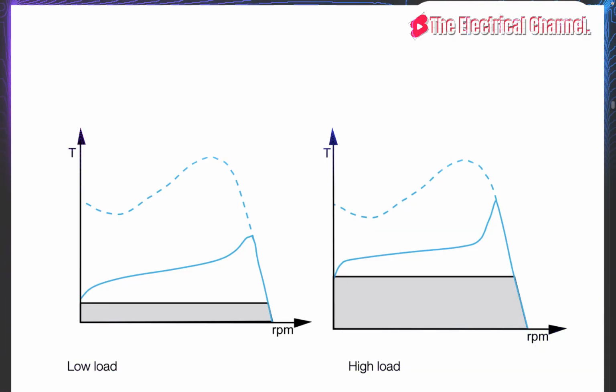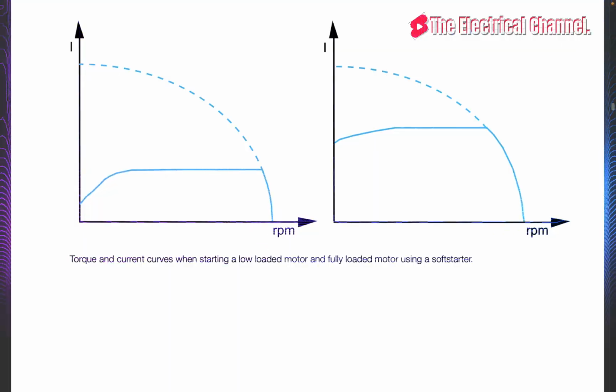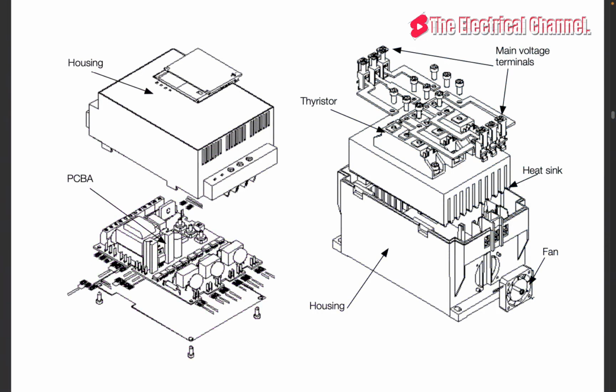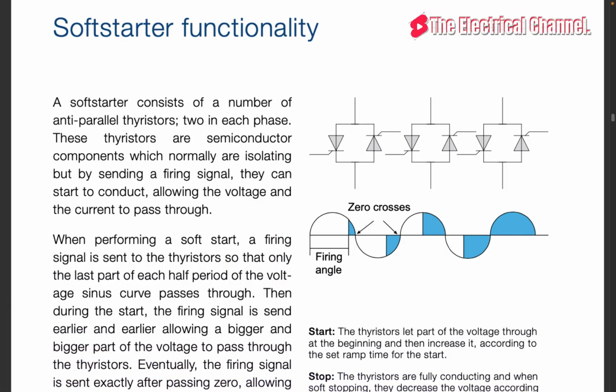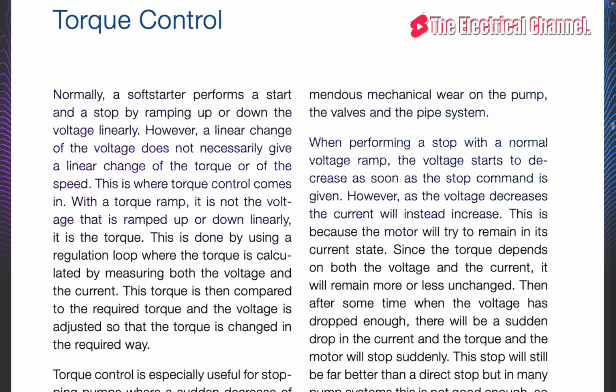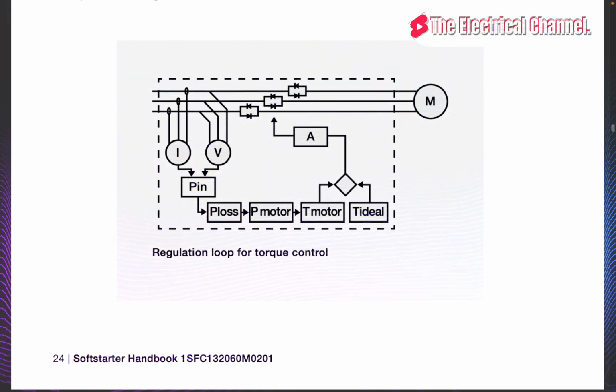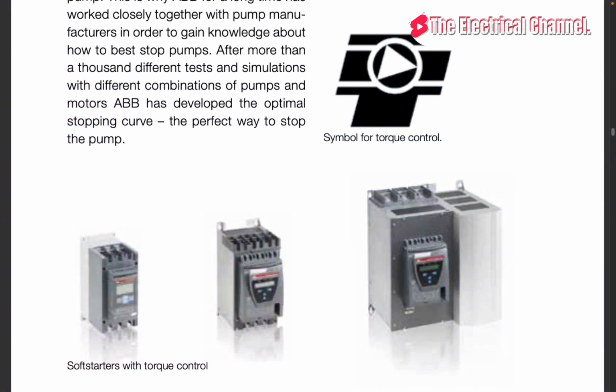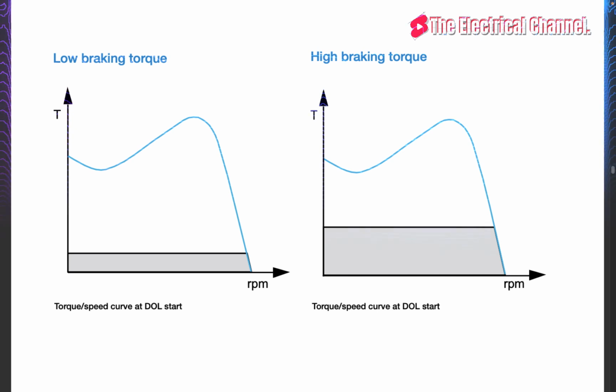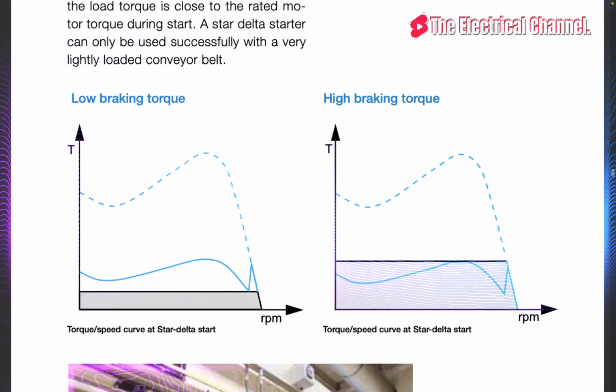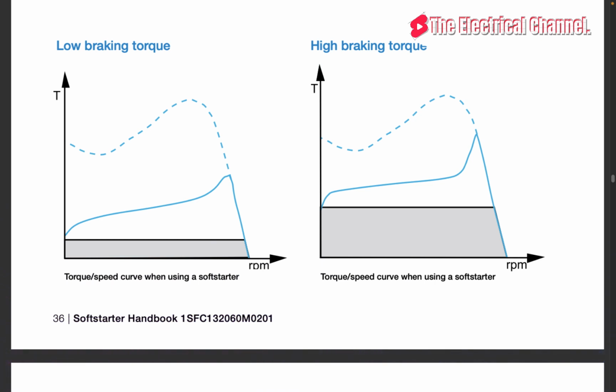End voltage is the voltage level that the softstarter ramps down to during the set ramp time of a stop ramp. At this point, the motor shall already have stopped, and the softstarter will break the current to the motor in order to avoid unnecessary motor heating. Adjustable rated motor currents. This makes it possible to set the motor rated current on the soft starter for the used motor. This setting will affect other values as well, such as the trip level of the electronic overload protection and other protections, but also the level of the current limit function.